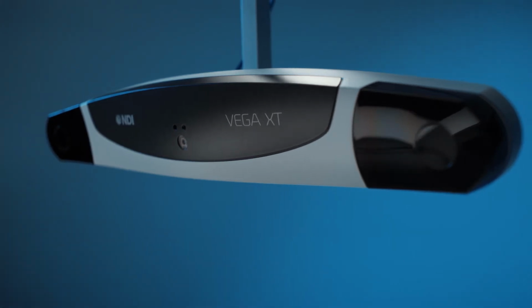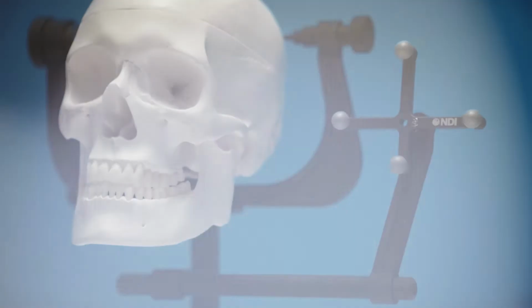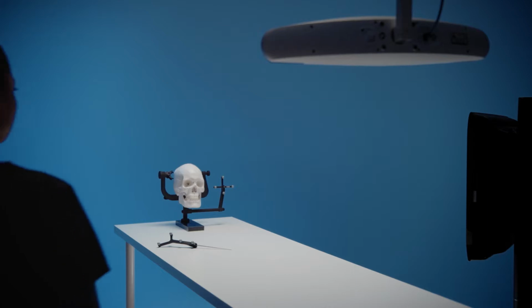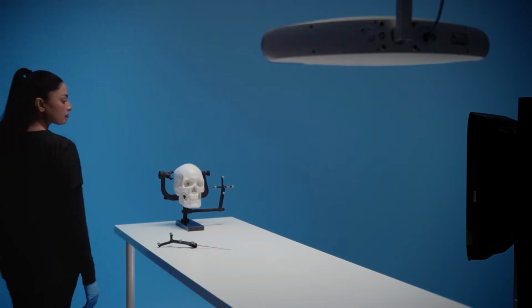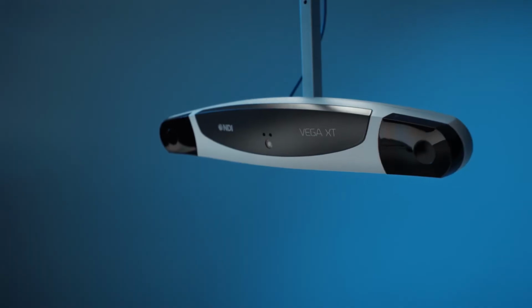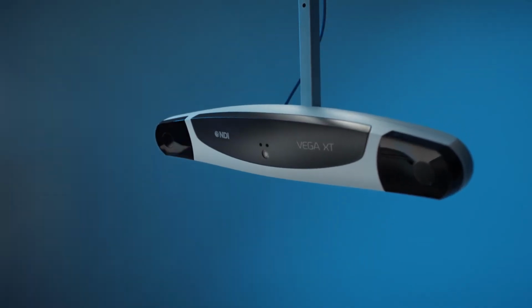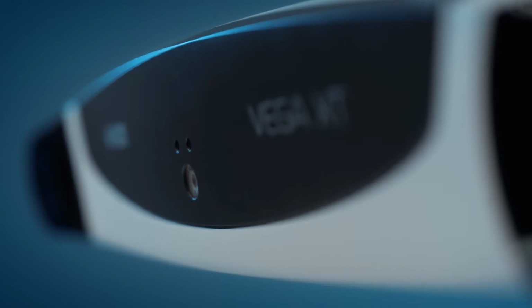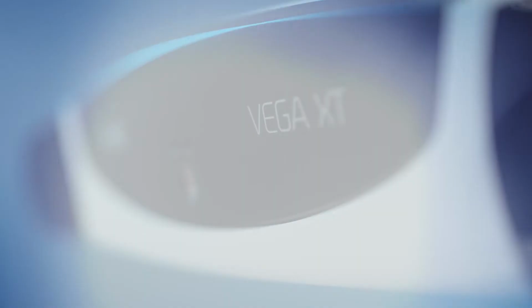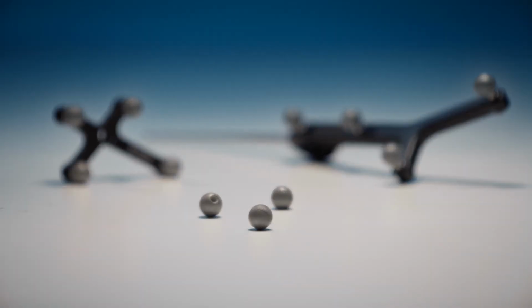The Polaris optical measurement solution is like GPS navigation for OEM image-guided surgery systems, using near-infrared light to locate and track surgical instruments in 3D space. The Polaris optical measurement solution consists of two core components, an optical tracker and navigation markers.